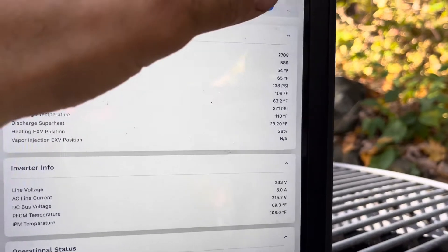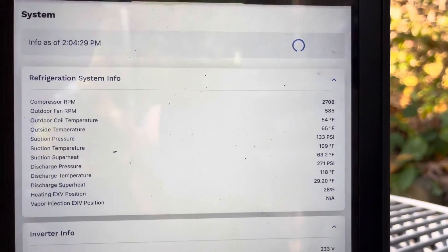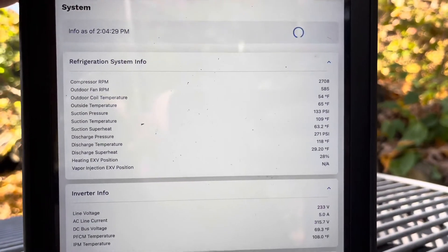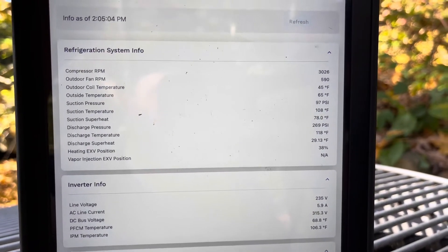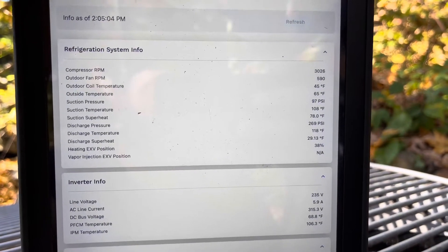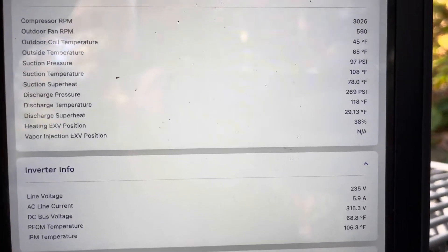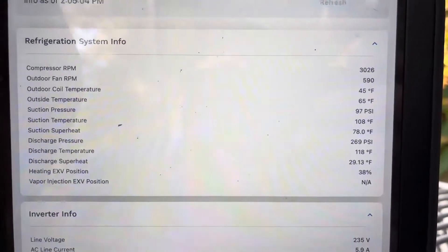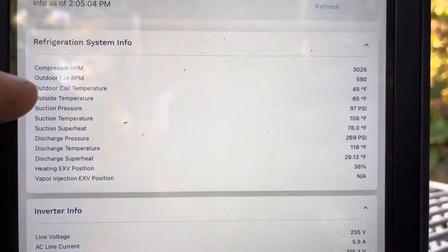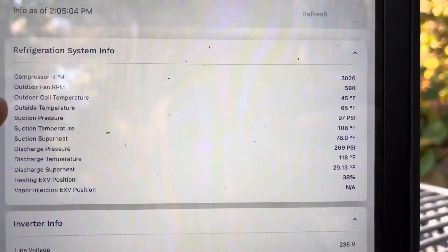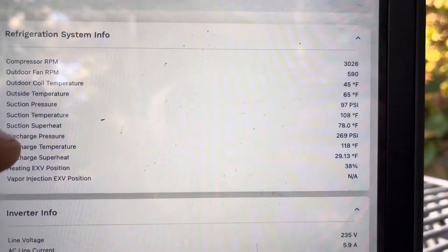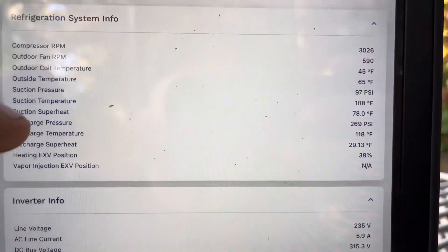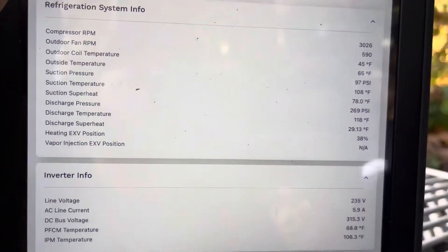Now refresh—something changed, so it'll ask you to refresh when something changes. I think 30-26. So what do we have for PSIG? We're in heating mode right now. Suction we're at 97, discharge 269. That's a great clue.